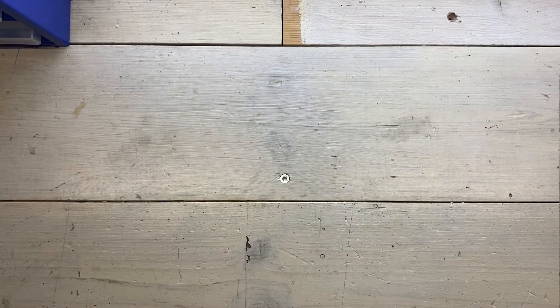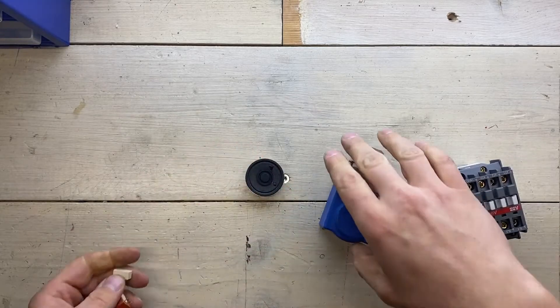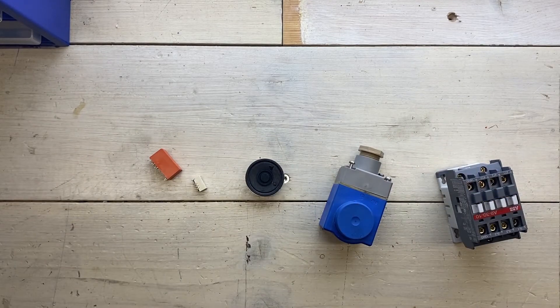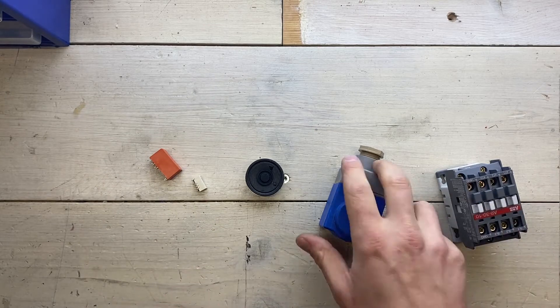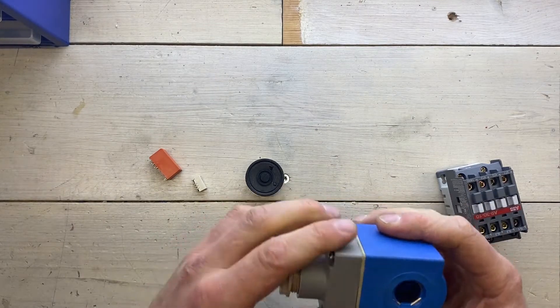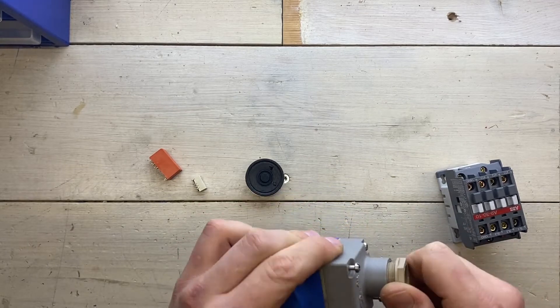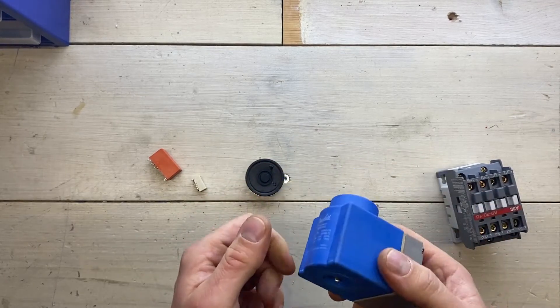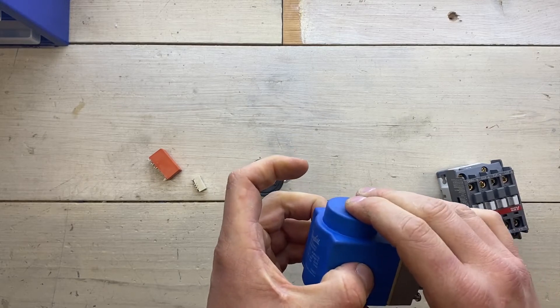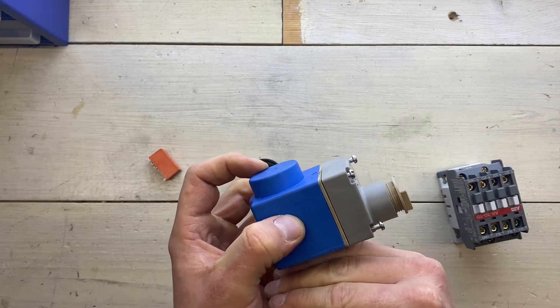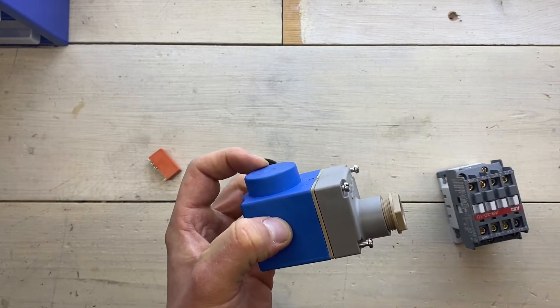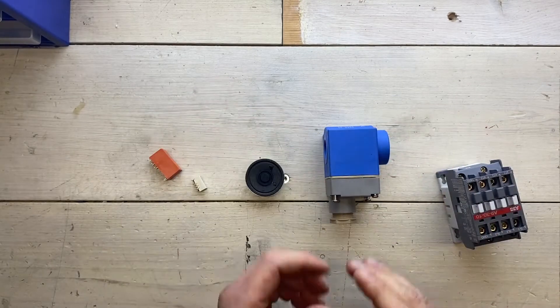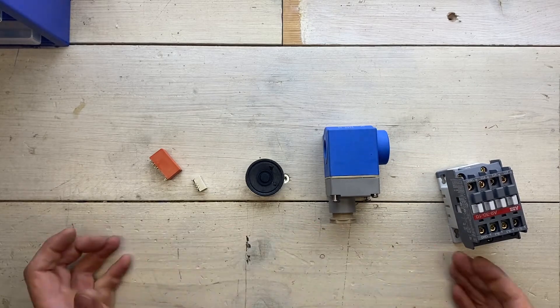Now I have one more component I'm going to talk about today. And all of these components have it in common. And you guessed it it's coils or solenoids more specifically. Now this entire thing is a coil. It's a 240 volt AC coil used to open and close water valves. So basically if this one is installed on a valve, I put 240 volts to it, this coil energizes and creates a magnetic field. And that magnetic field then pulls an anchor inside the valve that causes it to open. And if I remove the voltage it demagnetizes and the valve closes. And that's the only thing a solenoid does. It's an electromagnet. And all of these components contain them.